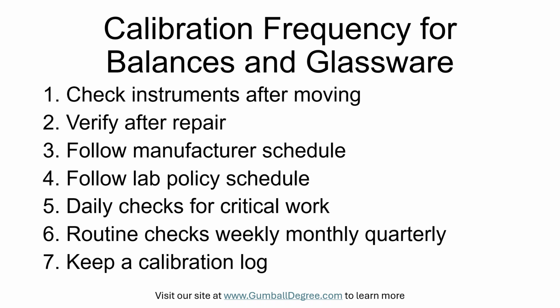Manufacturers usually give a schedule, labs have their own rules, and critical experiments may need daily or before each use checks, while routine instruments may be checked weekly, monthly, or quarterly depending on risk. Calibration after repair or after moving an instrument is important because bumps and jolts can change how it reads. Keep a log so you know when the last calibration happened and what the results were.